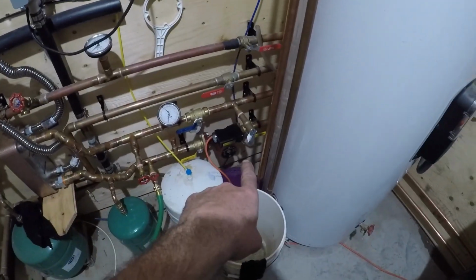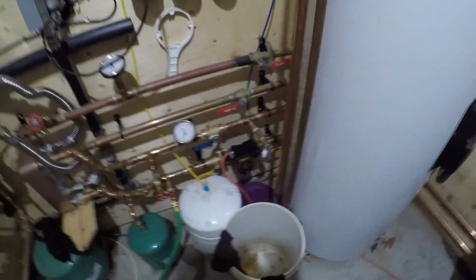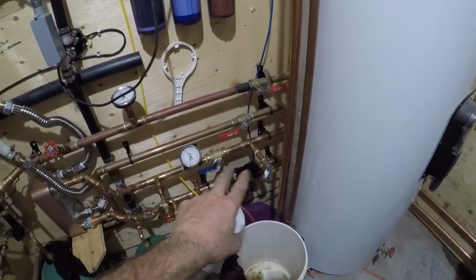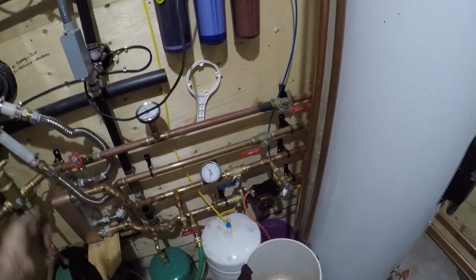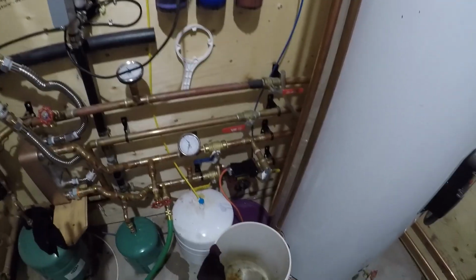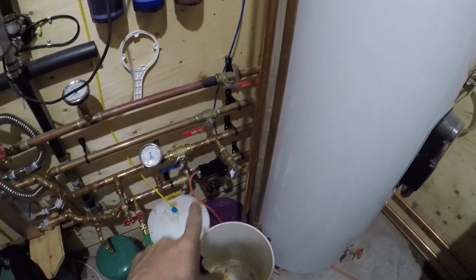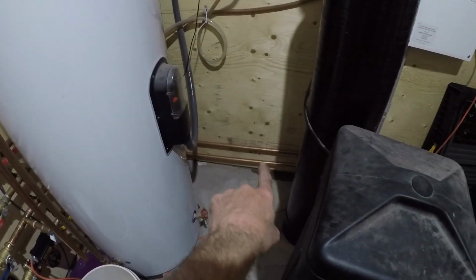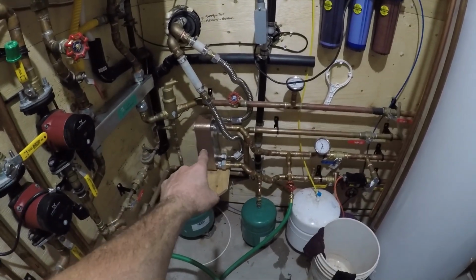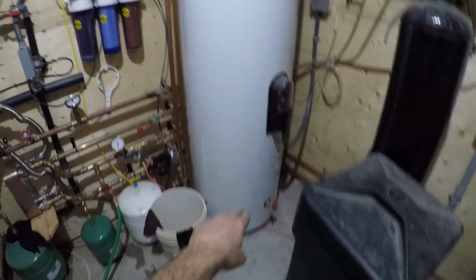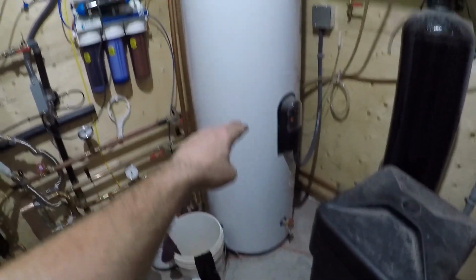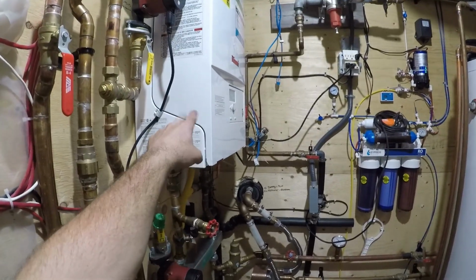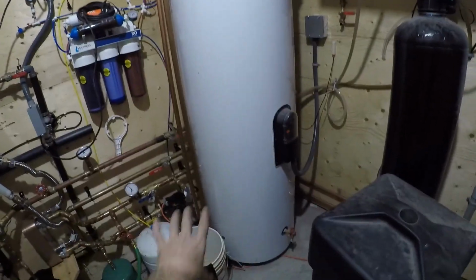So this circulator pump's running. It's going to be hooked up to the automation system, so it will turn on once the boiler gets up to 150 degrees, or the wood stove gets up to 150 degrees. Once that component is added in, this pump will turn on to circulate through the buffer tank. So the wood stove and the heat exchanger from the outdoor boiler both heat the bottom half of this tank. Well, actually the whole tank, but it starts at the bottom, whereas the gas boiler only does the top half, so the bottom is always kind of cold.